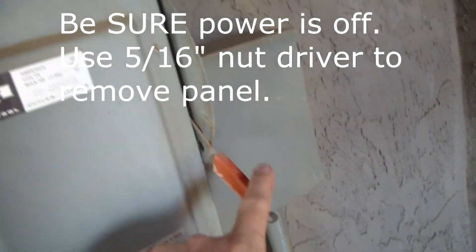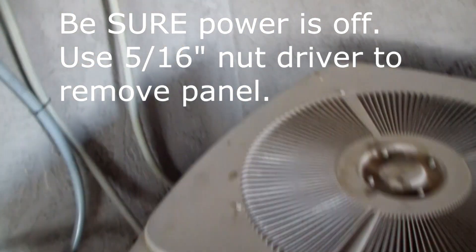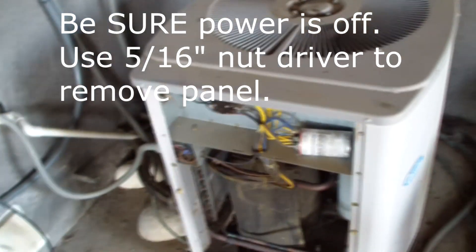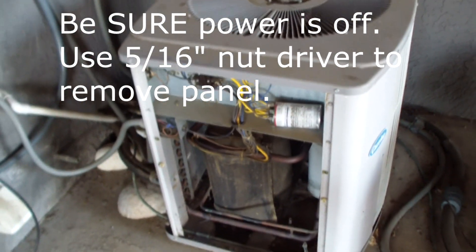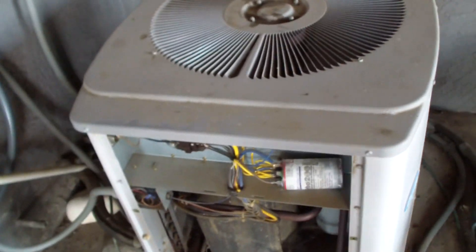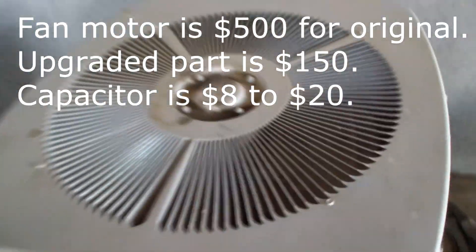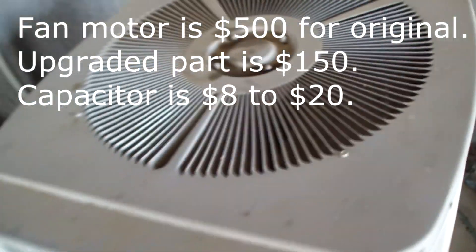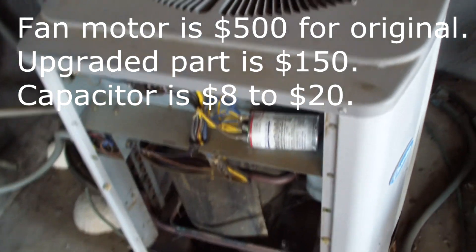So the first thing I did was turn off the main power going in here, the 240 volts going in, and take off the side panel. The plan is, it's either the motor - the motor that blows the fan, this has got a quarter horsepower motor - or the capacitor.